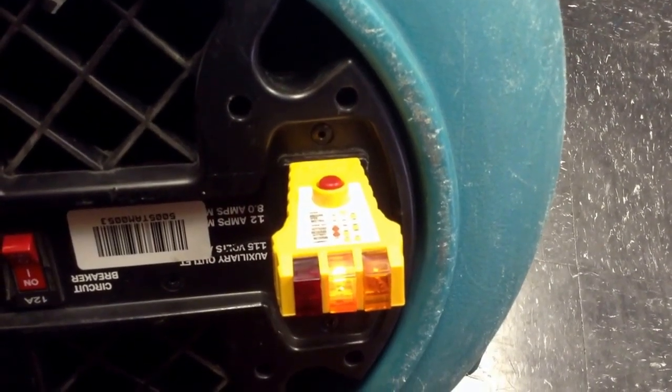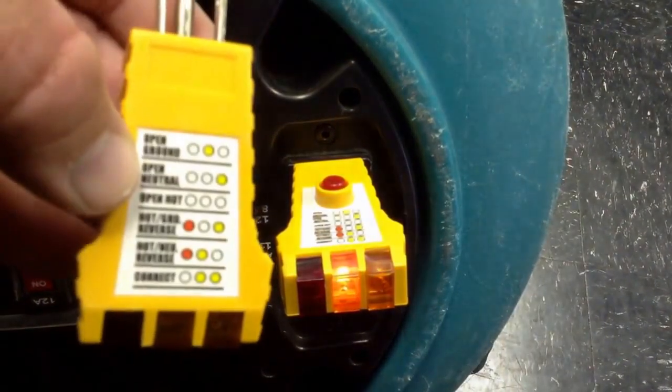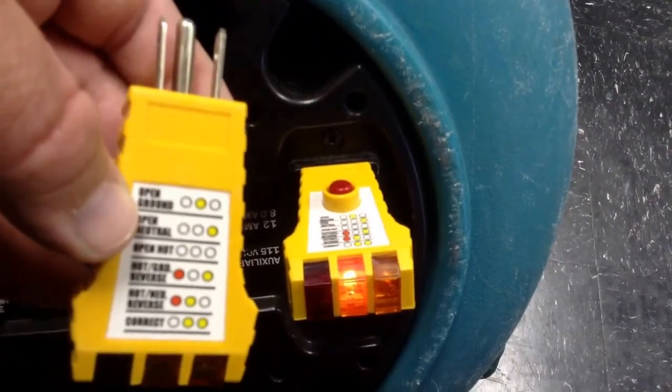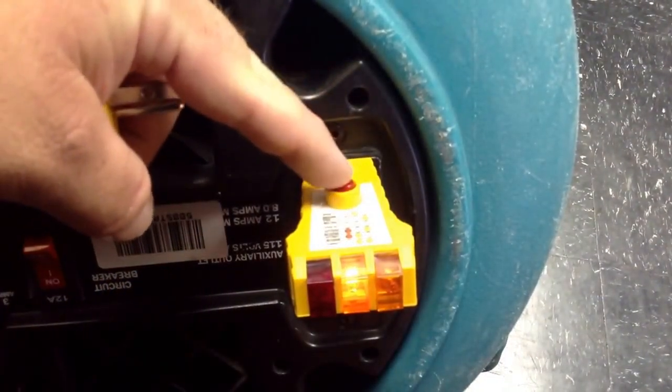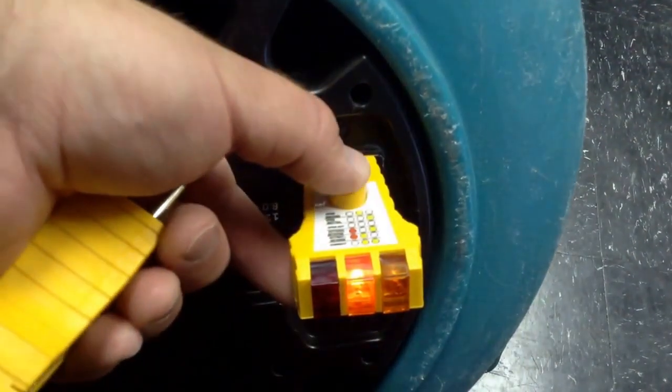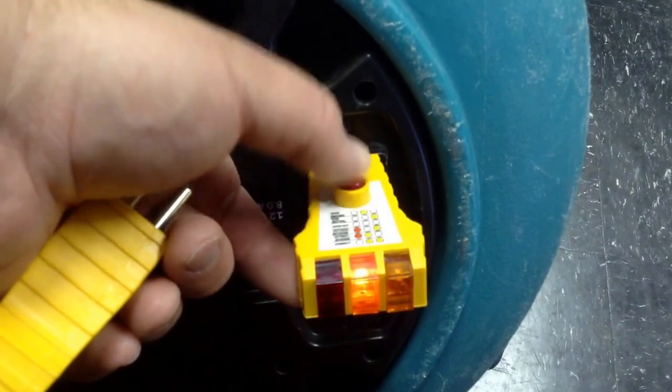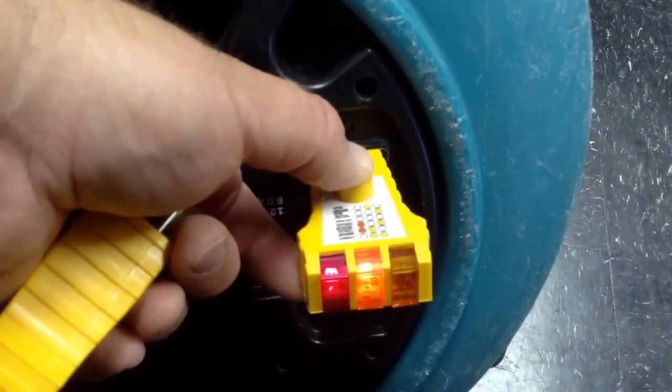As we can see here on this GFI plug we have one yellow light in the middle, meaning we have the top scenario here which is an open ground. So if we press and hold this, if it doesn't trip the GFI it means it's wired incorrectly. So as you can see when it tries to trip the GFI it now turns on the red light on the left.